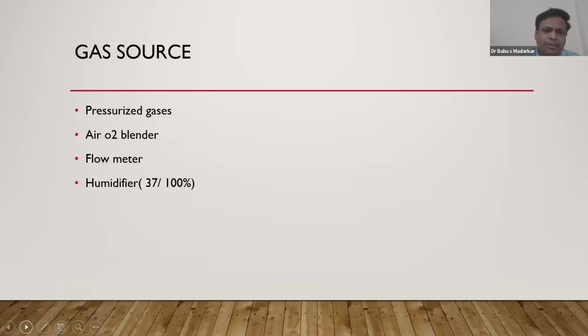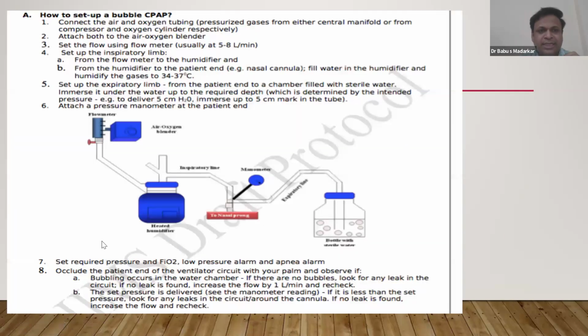For the gas source, there has to be a blender of oxygen and air, and we need to have a flow meter with a humidifier in place. This is extremely important when we are offering CPAP. So this is the flow meter, and this is the air blender. The flow in the air comes from here as per the blender. Before this, there is one oxygen source and one air source. Blending happens. It goes into the humidification chamber. There it gets humidified, and from there it goes to the inspiratory line and through the nasal prongs.